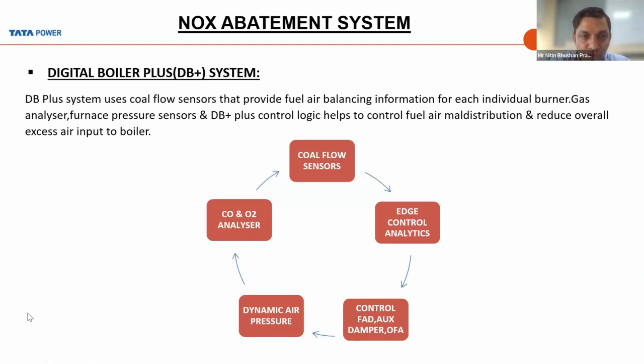The digital boiler plus comprises major components, the first being the coal flow sensors. There is a set of 2 coal flow sensors in each coal pipe that measures fuel in each burner. The coal flow sensors provide fuel-air balancing information, and they are located at each coal pipe for finer control of the air injected. The edge control assembly analytics, a discrete controller assembly, gives data and sends commands to individual dampers for the fuel air and auxiliary air, and biasing is also provided in the DCS.